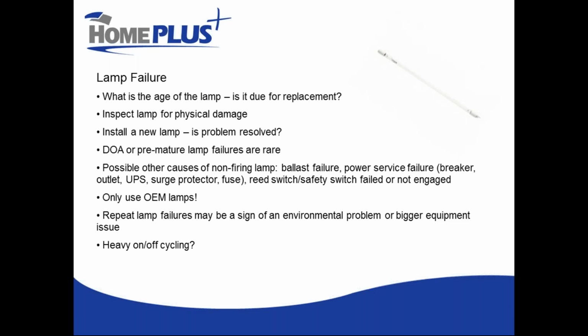I've had a few cases where people have replaced the lamp with a brand new one and it doesn't fix the problem, so then they assume that the lamp that they had on the shelf is also bad. And I would venture to suggest that multiple lamps not firing correctly in a system probably means it's not the lamp. So if your new lamp has the same problem, definitely start looking for causes outside of lamps.